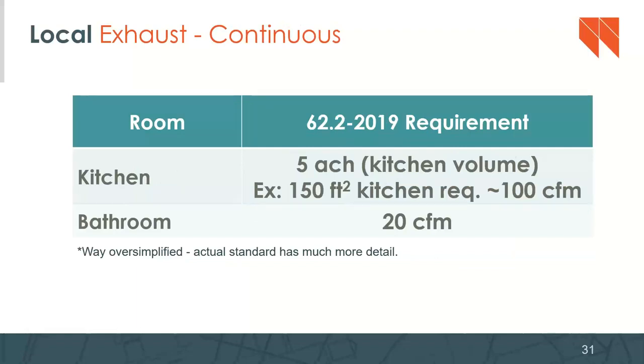What about if that local exhaust system runs continuously? So these are still in the areas, these rooms of concern. What if you want to design a system that is continuously going to pull air out of the bathroom or the kitchen? For a bathroom, it's pretty easy. We want to see that that is 20 CFM. It's operating all the time, but at a minimum, the flow rate is 20 cubic feet per minute. In the kitchen, it's a slightly different calculation. So 5 air changes per hour, and it's based on the kitchen volume. So you need to do a takeoff to figure out what the kitchen volume is. So for example, a 150 square foot kitchen, I think that is probably with 8-foot ceilings, if I had to guess, you're going to need to provide about 100 CFM continuously.